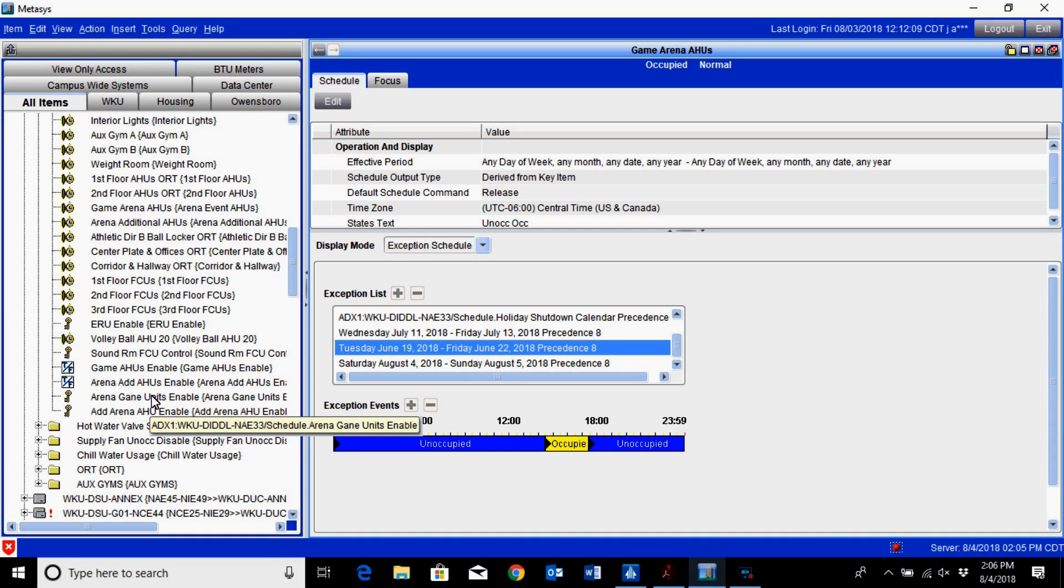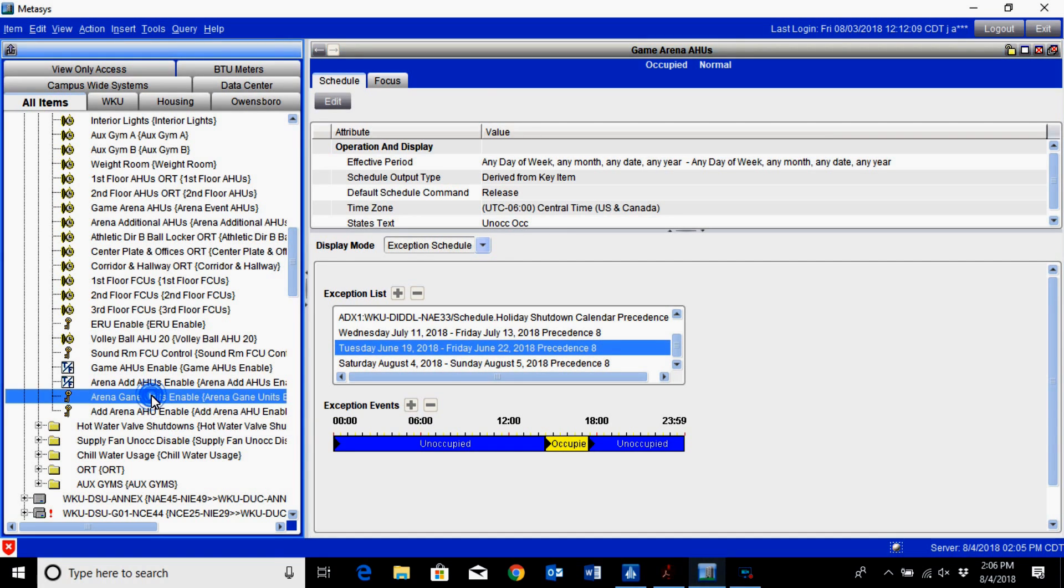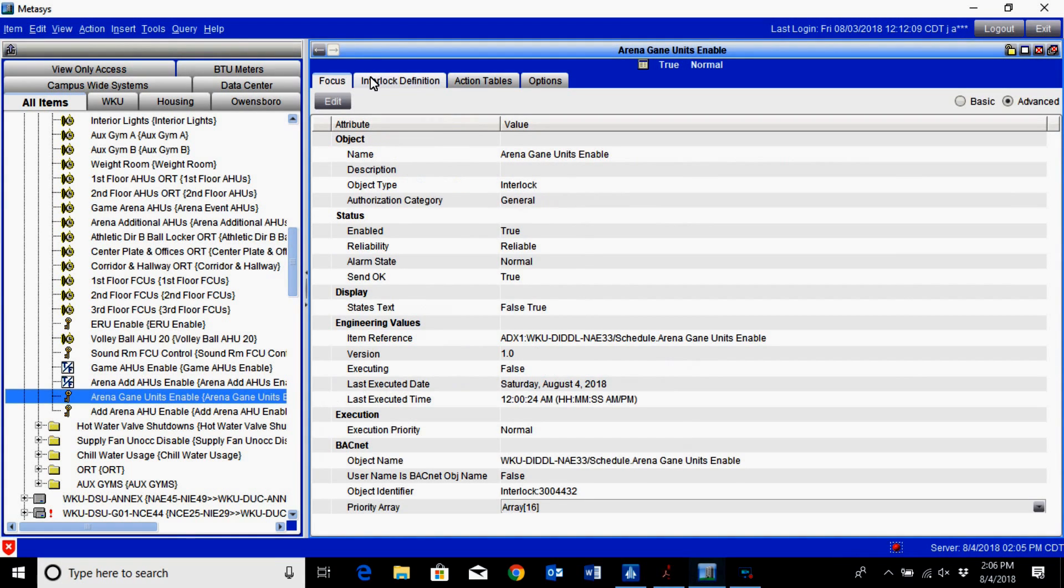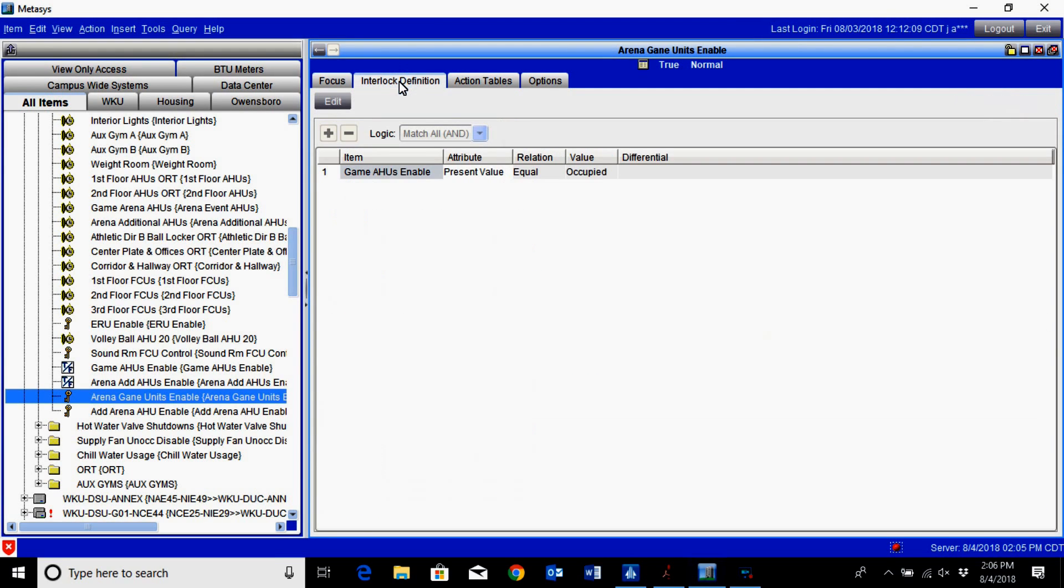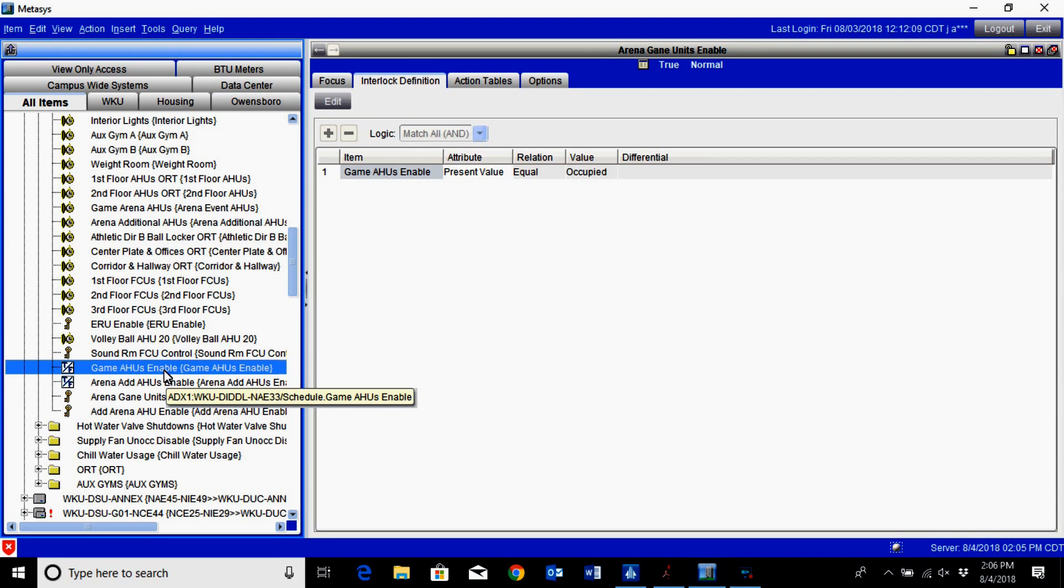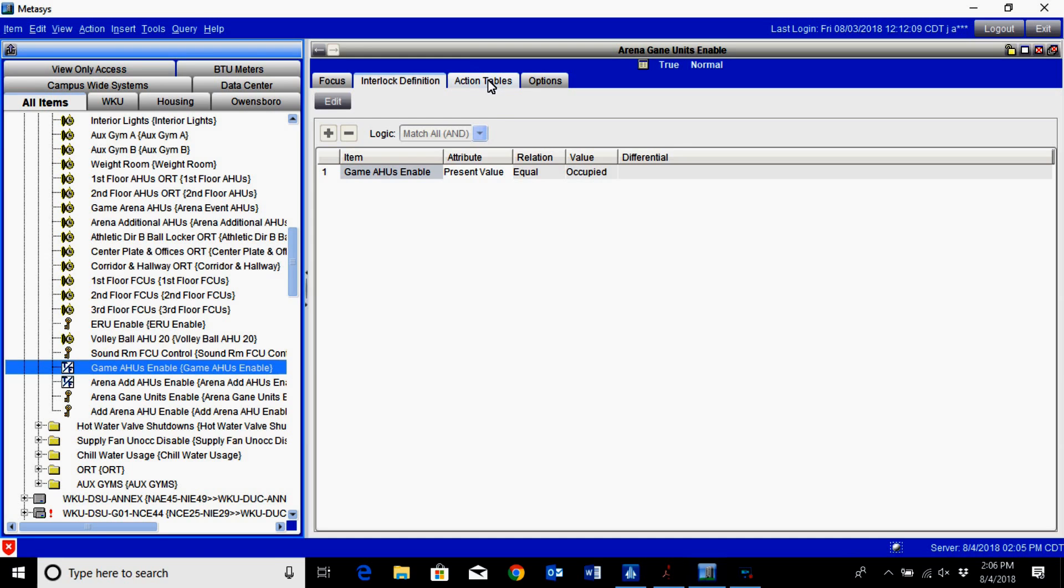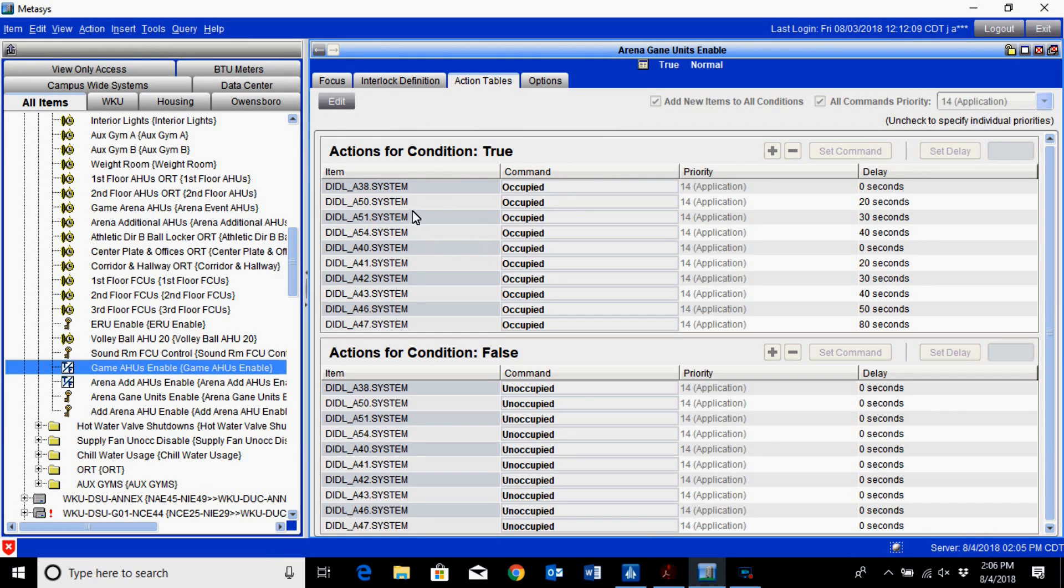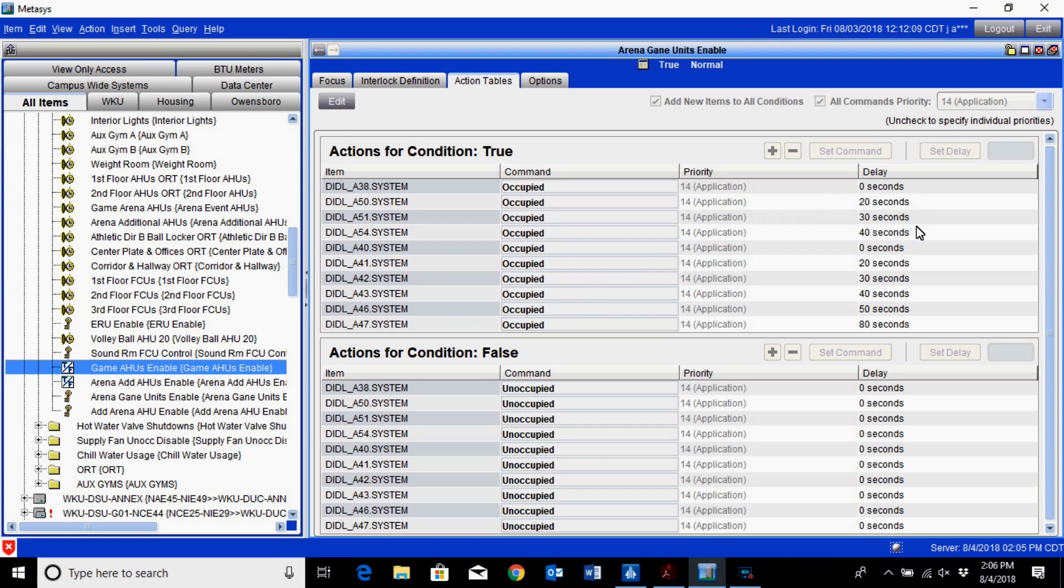Once you have that particular binary value scheduled, the next step is to create an interlock. Underneath the interlock definitions here is that particular point, the game AHU enable. This is what this interlock is looking at. If this particular value is occupied, underneath our action tabs it is going to begin bringing up the air handlers at different times.